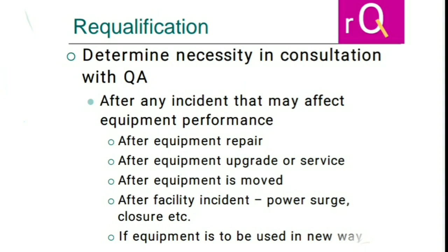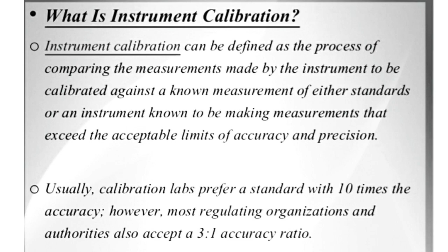When you suspect that the accuracy of the measurements being produced is questionable. If there were any repairs or requalification of the instrument, include them as part of the calibration schedule. Depending on the task and process, some require calibration to be conducted before the work starts. According to the manufacturer's recommendation, we have scheduled our instrument calibration.